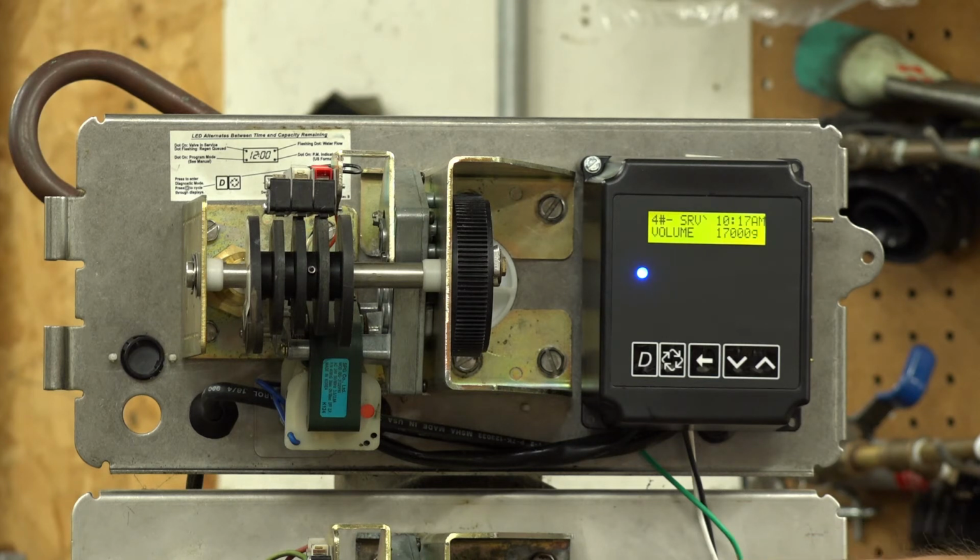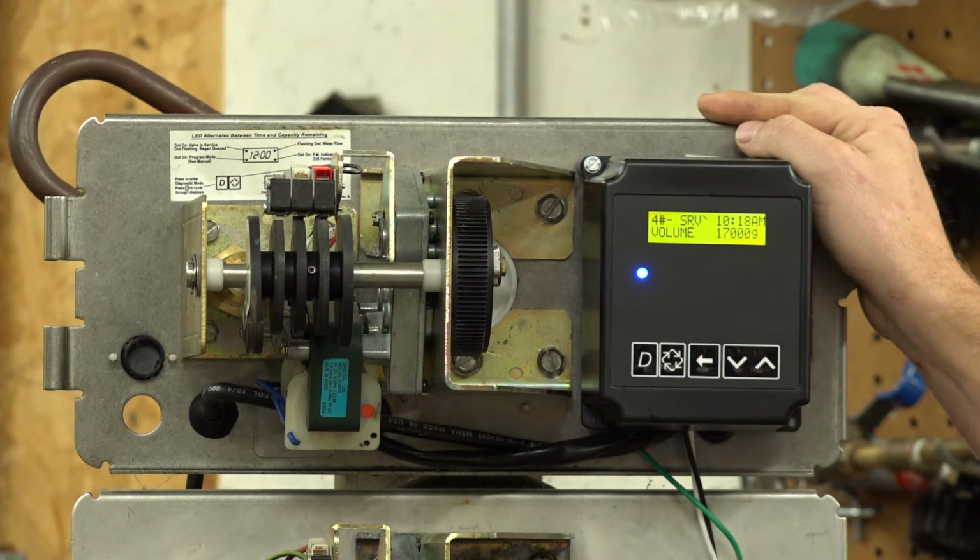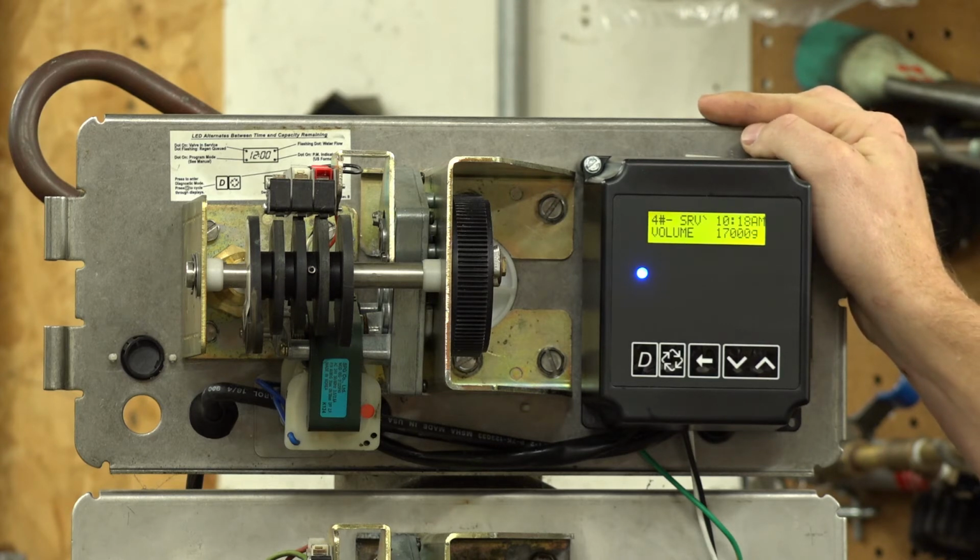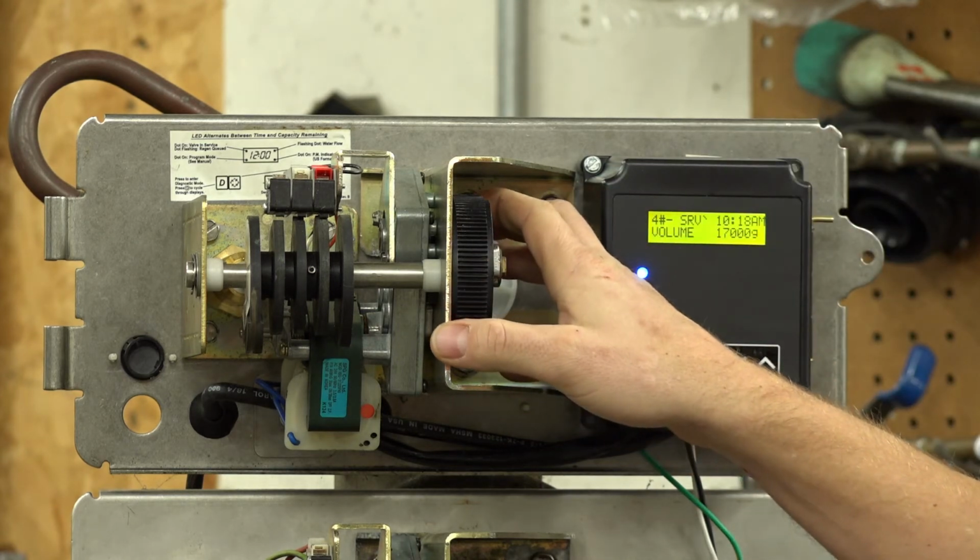That's mainly going to be on twins, or if the application is such that they cannot have hard water go through to the machine or the process. In some cases, they'd rather no water get through than hard water. So that's something you always need to verify every time you walk in. Every time you do a rebuild on a valve, you want to verify that you have the right lower piston in the valve. The upper piston is the same on both because that's your regenerative piston.